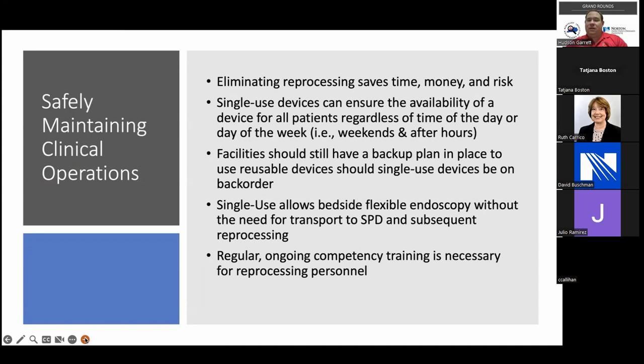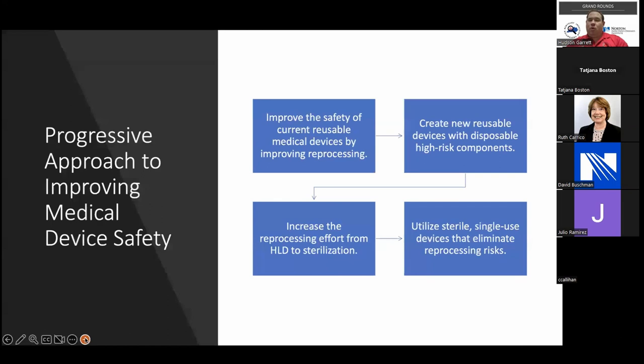We're never going to get rid of our people and personnel involved in this process, but we want to eliminate as much of the known risk as possible. That's really where this progressive approach comes from: start with your baseline, look at disposable componentry, move from HLD, high level disinfection, to sterilization, and ideally get to a point of single use if the device category has something with 510K approval from the FDA.